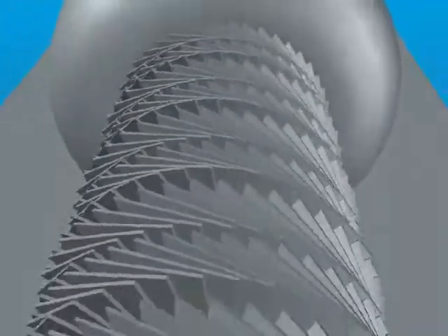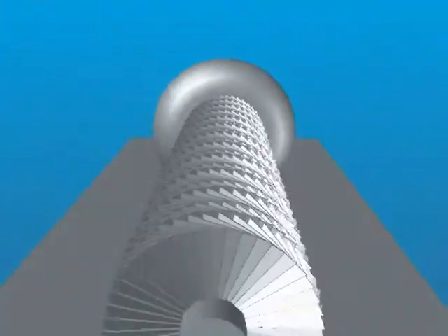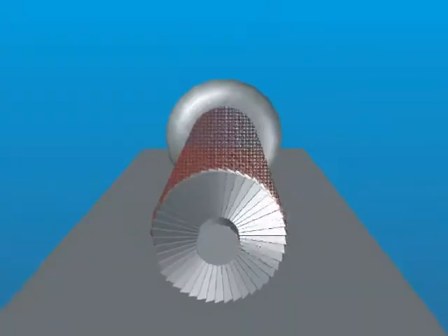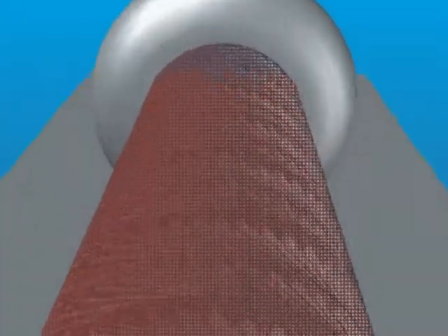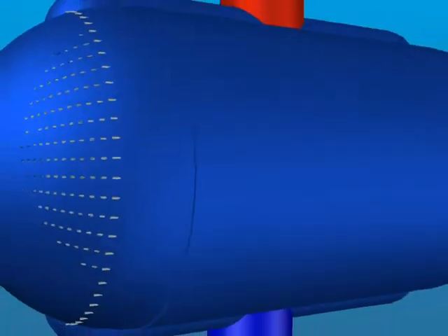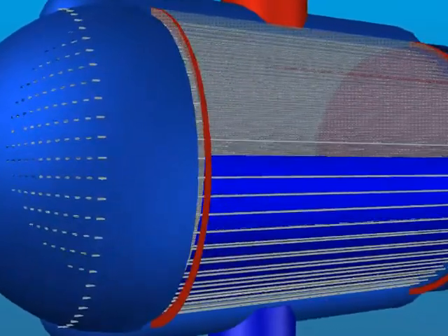Reaching the operational depth of the system, the vapor then enters a turbine housing, where it is directed by stators against the vanes of the turbine to produce mechanical energy. The spent vapor enters the condenser, which is essentially the evaporator in reverse. The vapor is condensed back to fluid as it flows over the condensing tubes, which contain the 4-degree water flowing through the pipes.